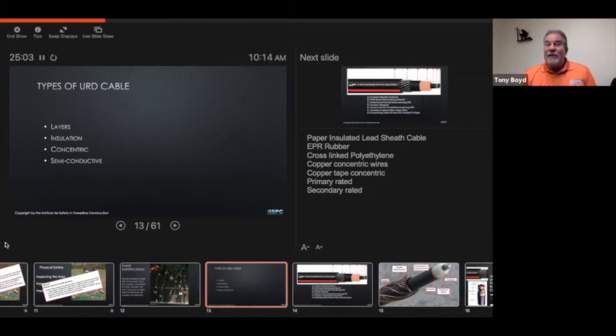Now we're going to get into the cable itself, which is why everyone is here, cable splicing. So we'll talk about the different kinds of layers of cable, the insulation, the concentrics, the semiconductive layers. So there's paper insulated lead sheath cable, and you may be surprised that there are still hundreds of thousands of miles of paper insulated lead sheath cable still in use since the 40s and 50s. It was an excellent, well-made product, and a lot of the folks that are splicing and keeping this energized are retiring and don't seem to be passing on the knowledge they have to the younger folks, because we get calls on a regular basis to come do some training on paper insulated lead sheath cable.